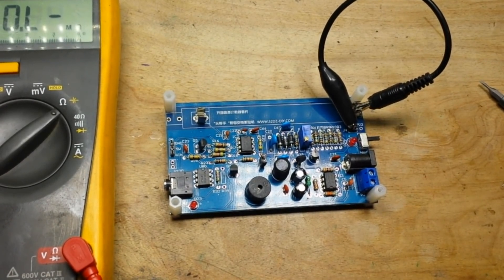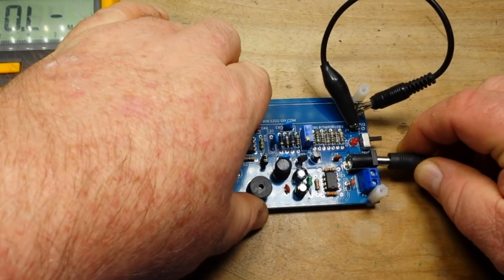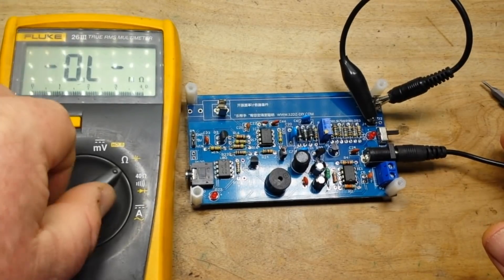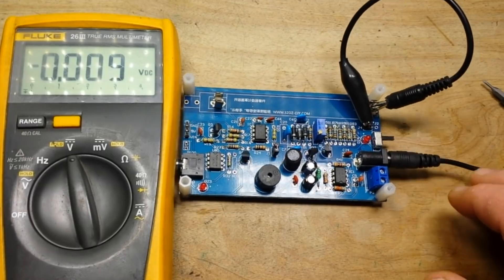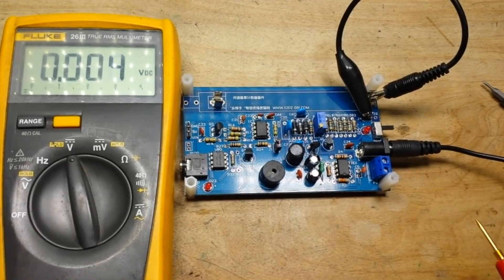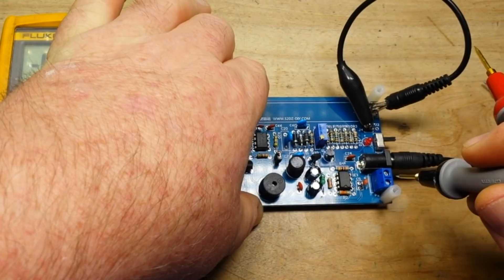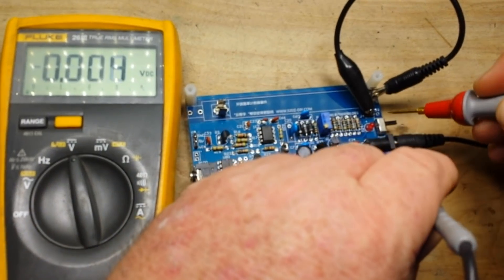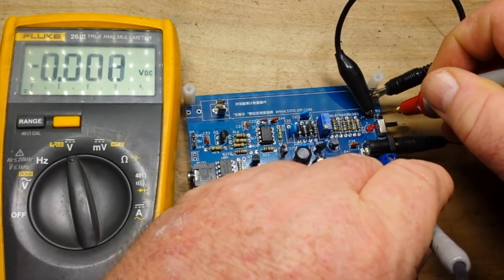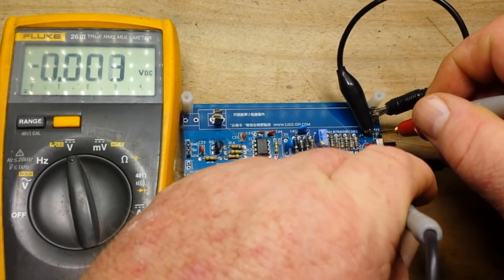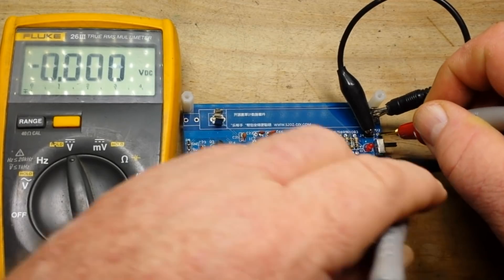We'll power it up. We're going to read voltage. We're supposedly looking for 57 volts at the J2 point. So there's a ground point. You're going to go here, nothing. J2 there, try this here, there's a ground here.